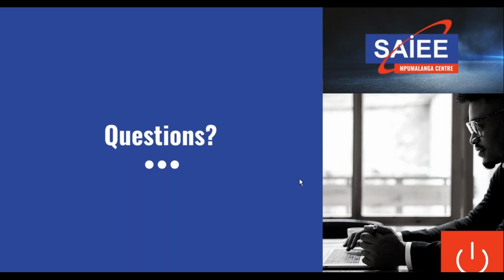So in the end, you need to ensure that you've got as accurate as possible information at design stage when you go that route, to ensure that you don't come up with any hiccups during commissioning. Correct. There's one additional issue, and that is you're jumping from one tap setting to another. It's not a smooth transition. Or you are starting just on one tap setting, and then you are bypassing that auto transformer once the machine gets up to speed. So that switching either between taps or bypassing from the auto transformer to the line can result in a current spike that, again, when compared to a solid state soft starter, you would not get.